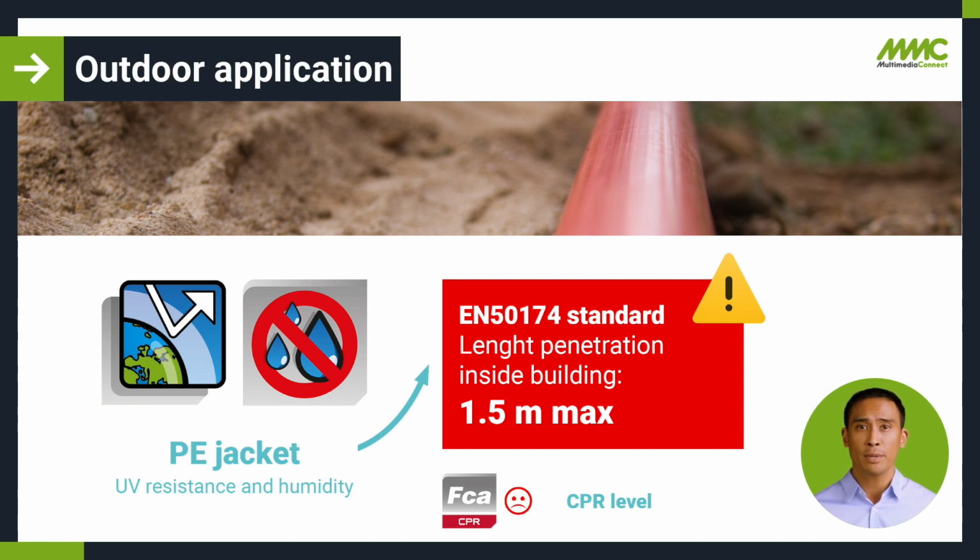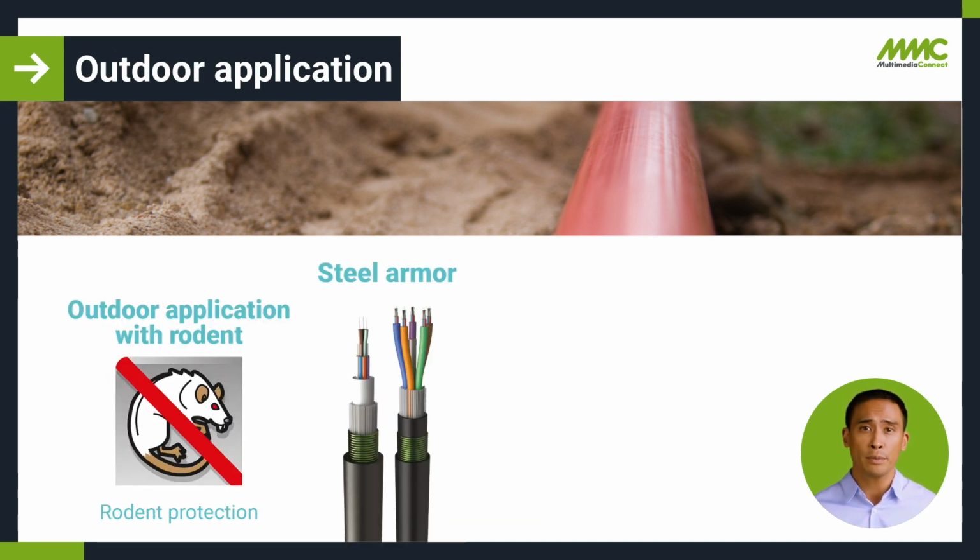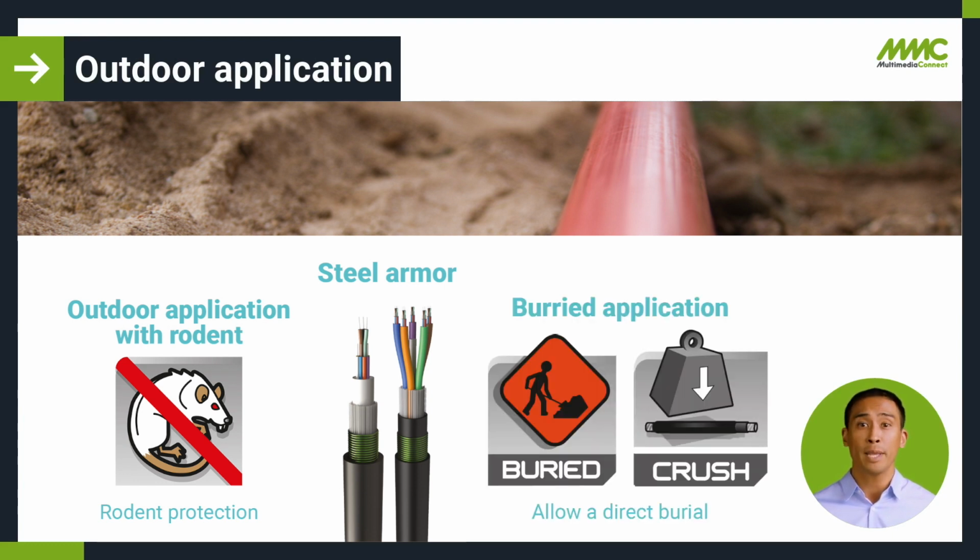So polyethylene cables are best for outside, and if I'm in an environment where rodents could come, such as rats and other small animals, an armored cable with steel insert is preferable, knowing that the armored cable can also be buried due to its high resistance to crushing.